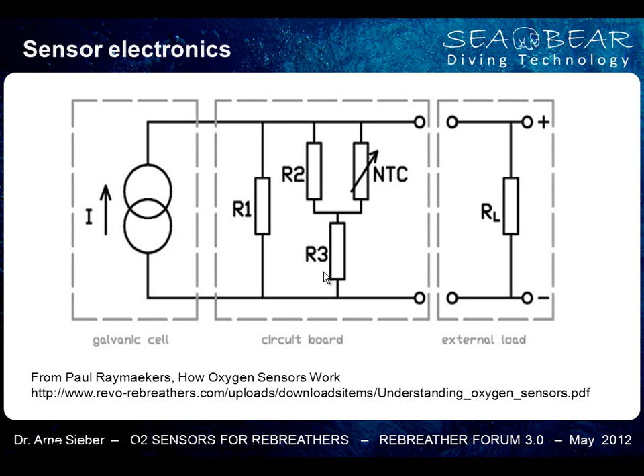So there we come to the sensing problem. Important for the sensor is: does the galvanic sensor have the same temperature as the sensing element? Typically in such sensors, the sensing element is mounted on a small PCB on the back of the sensor. So in a sensor for a rebreather, you put some kind of thermally conductive paste between this PCB and the membrane at the back, so you have very good thermal conductance between the temperature sensing element and the electrochemical sensor. This is for a sensor used in a rebreather.